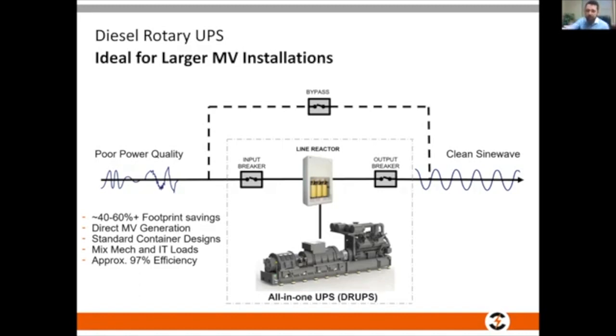I no longer have an ATS. Previously I showed the ATS up front feeding my diesel generator. Now I've moved my diesel generator in this setup. I've got my engine and my alternator, and I've added a flywheel. I don't show a rectifier, inverter, or battery bank, because I don't store energy in a battery—I store it in a flywheel. I've mechanically coupled my flywheel, which is my storage device, to my diesel generator. Just by that small change, I've already simplified the one-line. I no longer have the ATS, the diesel generator in its old position, the rectifier-inverter, the batteries, or the air conditioning that goes along with those electronic components.